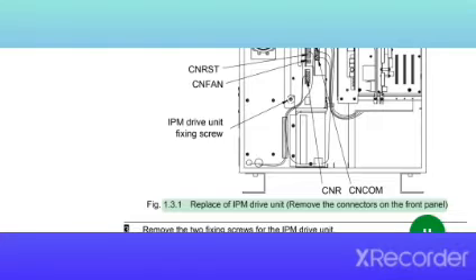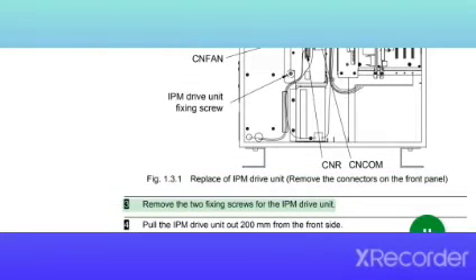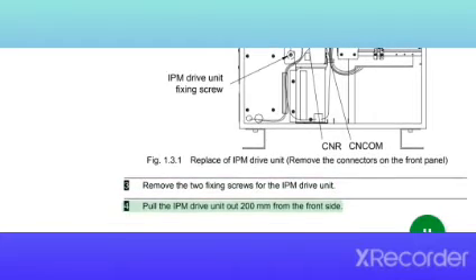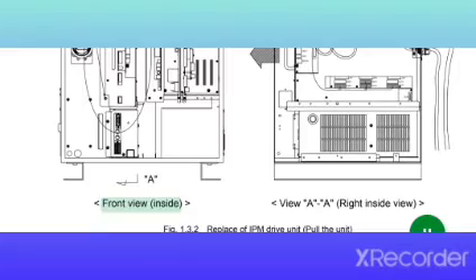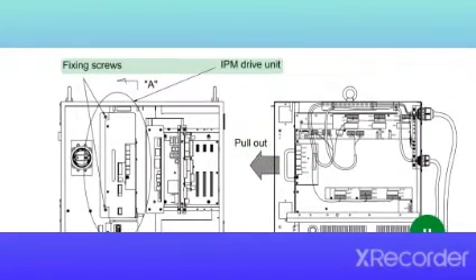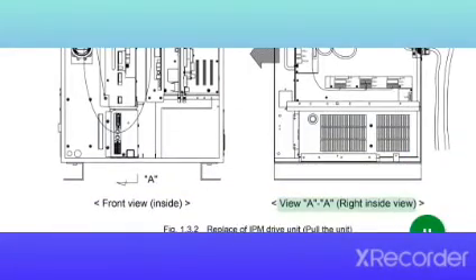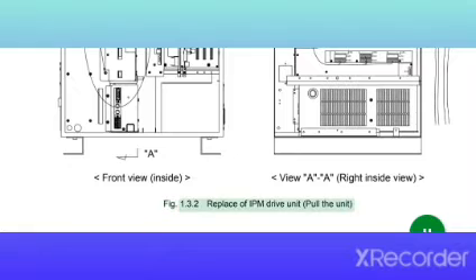Remove the connectors on the front panel. 3. Remove the 2 fixing screws for the IPM drive unit. 4. Pull the IPM drive unit out 200 mm from the front side. Front view inside. A. Pull out. Fixing screws, IPM drive unit. View A-A, right inside view. Fig. 1.3.2 Replace an IPM drive unit. Pull the unit.